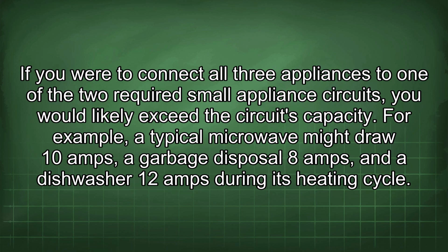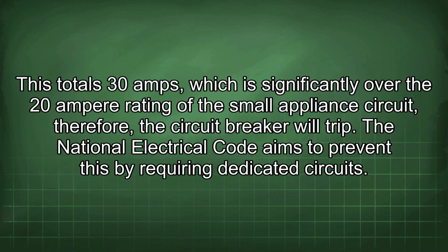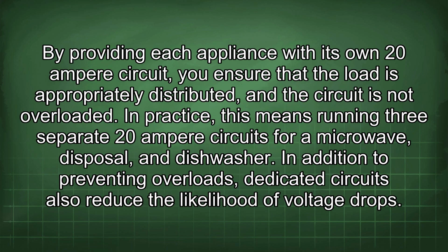If you were to connect all 3 appliances to one of the 2 required small appliance circuits, you would likely exceed the circuit's capacity. For example, a typical microwave might draw 10 amps, a garbage disposal 8 amps, and a dishwasher 12 amps during its heating cycle. This totals 30 amps, which is significantly over the 20-ampere rating of the small appliance circuit. Therefore, the circuit breaker will trip. The National Electrical Code aims to prevent this by requiring dedicated circuits. By providing each appliance with its own 20-ampere circuit, you ensure that the load is appropriately distributed and the circuit is not overloaded. In practice, this means running 3 separate 20-ampere circuits for a microwave, disposal, and dishwasher.